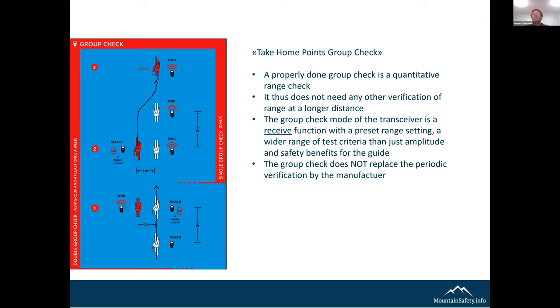However, the group check does not replace the periodic verification by the manufacturer. About every 3 years, one should send the transceiver in so it can be properly tested by the manufacturer. These manufacturer tests include a much wider variety of test criteria with a much narrower tolerance band.